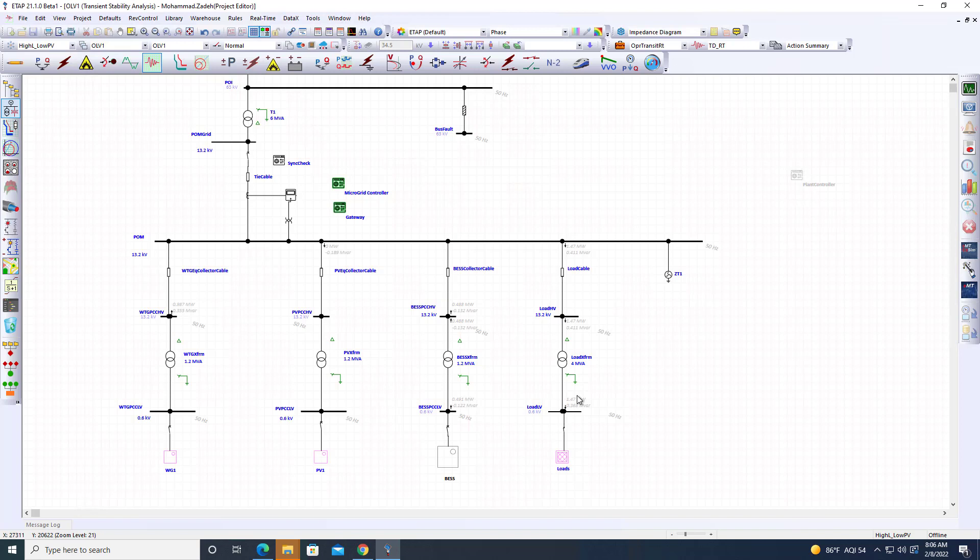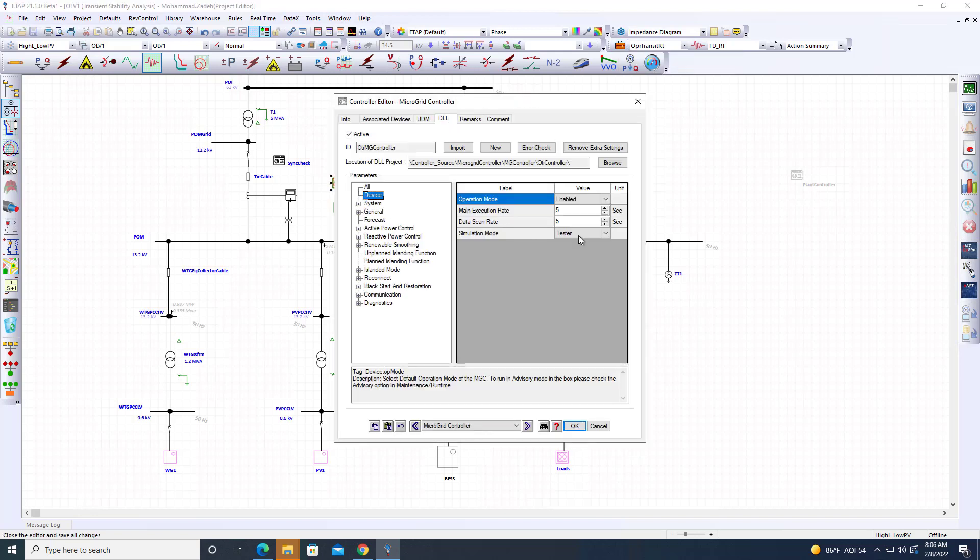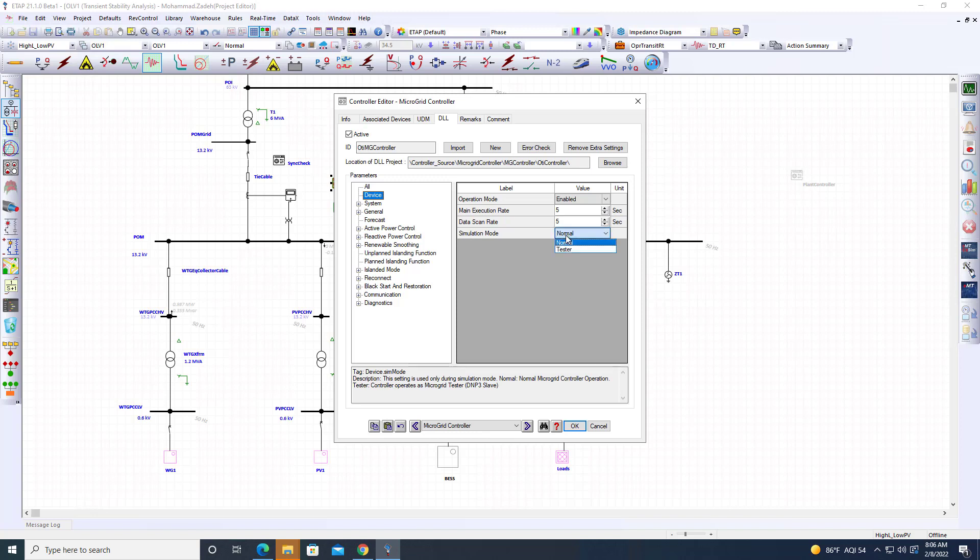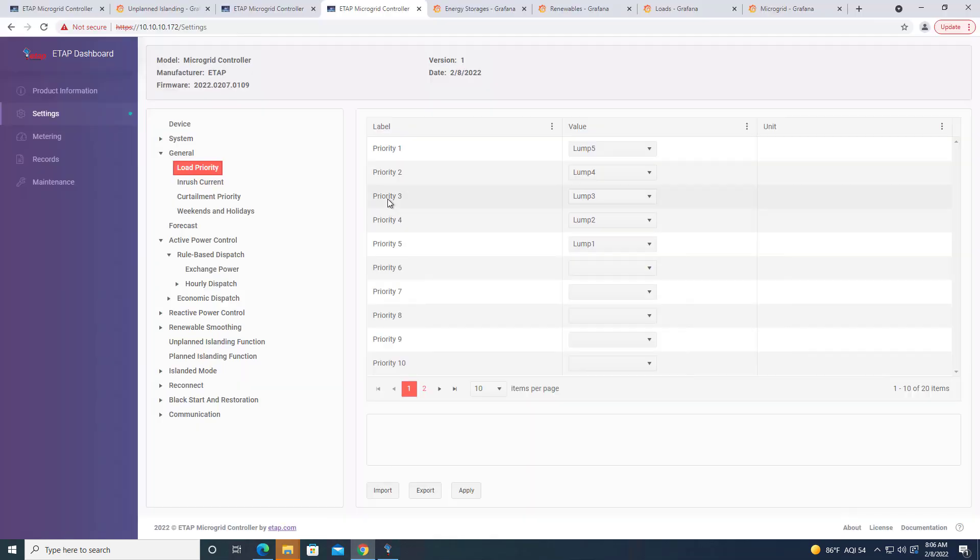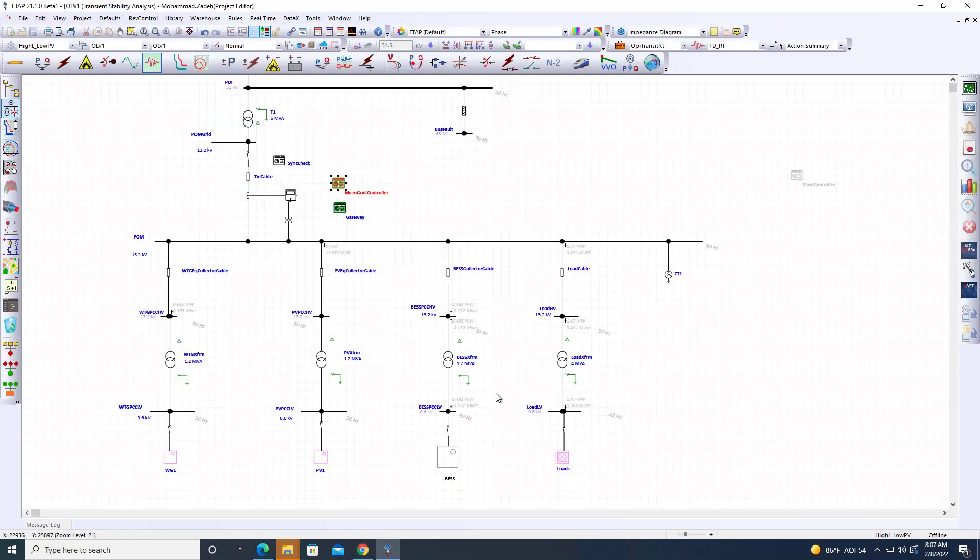We'll see how the microgrid controller actually transitions this microgrid from grid connected to islanded mode. We looked at the study case. The other thing we need to look at here is that we have a setting for simulation mode. If it is normal, it just runs the pure simulation. If I run tester mode, it runs it in a real-time manner. But the logic is not getting executed here. The data is transferred over communication to the hardware. It's like a hardware in the loop and hardware processing it and sending the output back to ETAP where the system is.